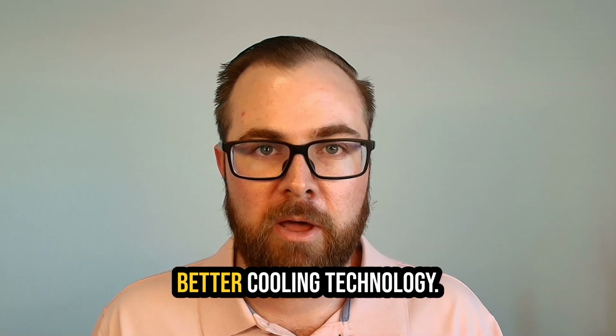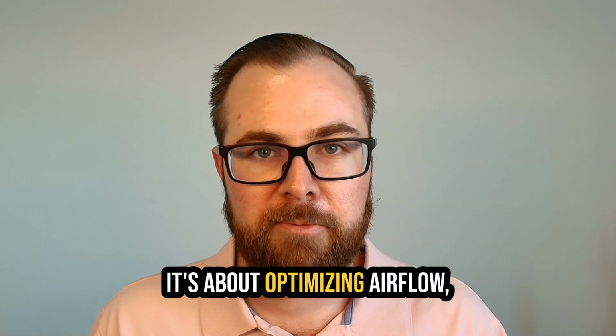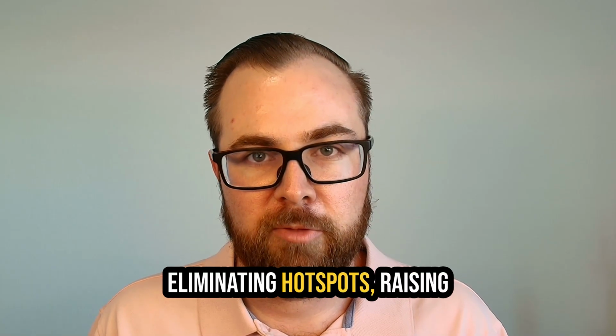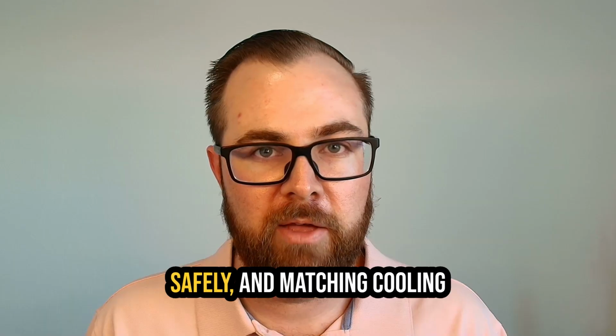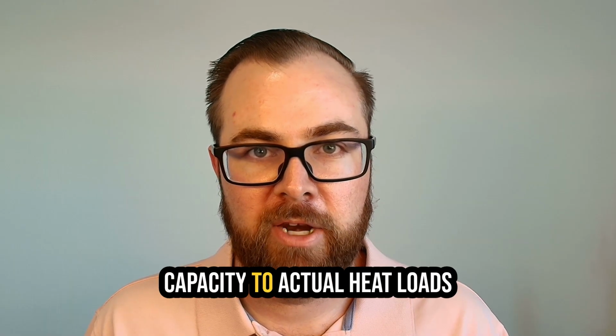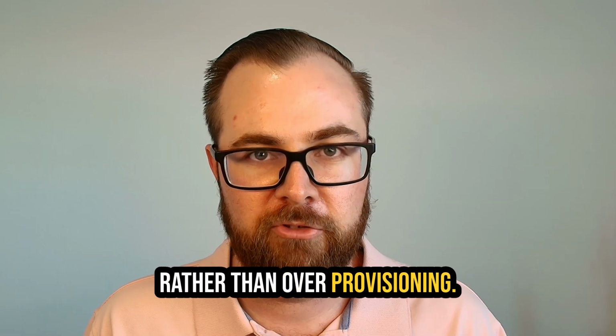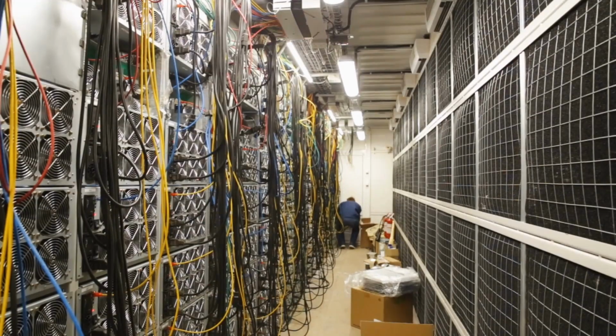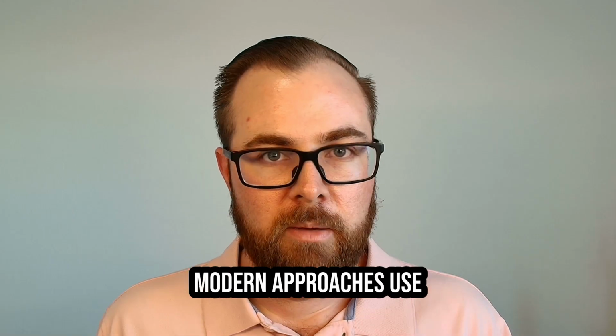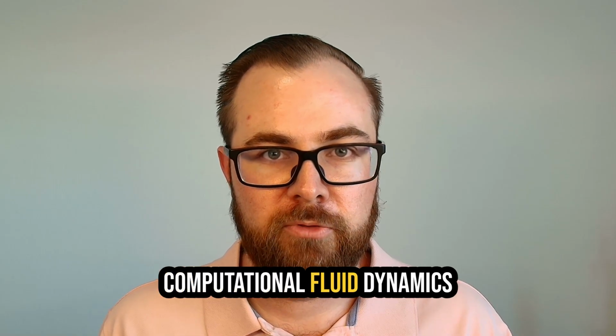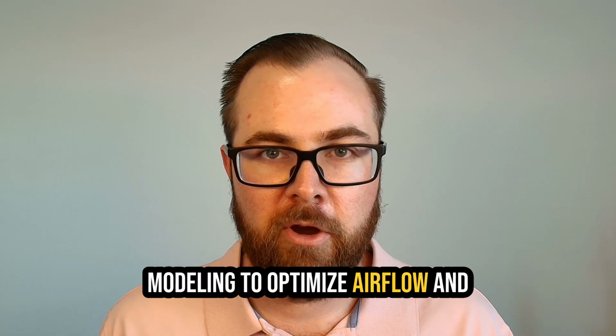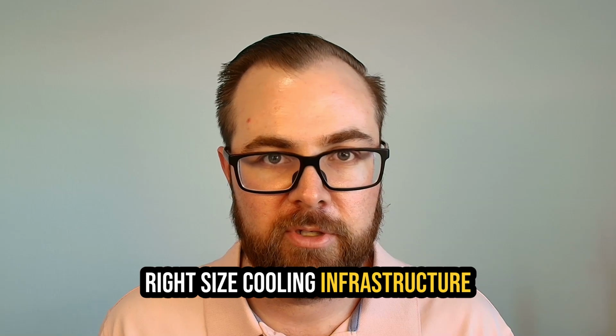Improving isn't just about better cooling technology. It's about optimizing airflow, eliminating hot spots, raising temperature set points safely, and matching cooling capacity to actual heat loads rather than over-provisioning. Many older facilities were designed with excessive cooling capacity because of conservative assumptions. Modern approaches use computational fluid dynamics modeling to optimize airflow and right-sized cooling infrastructure.